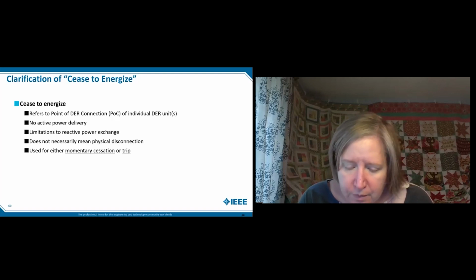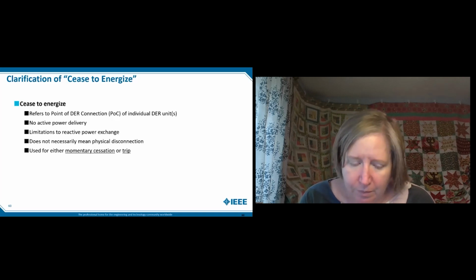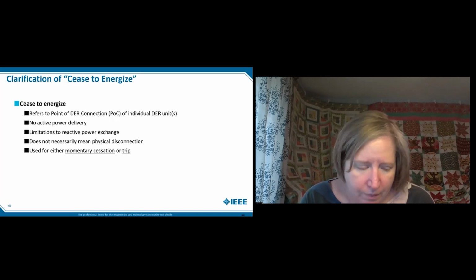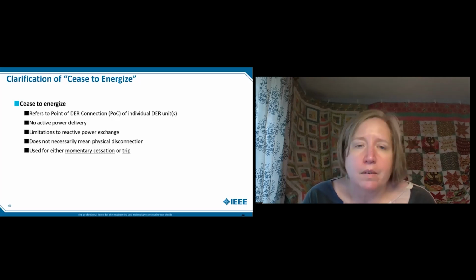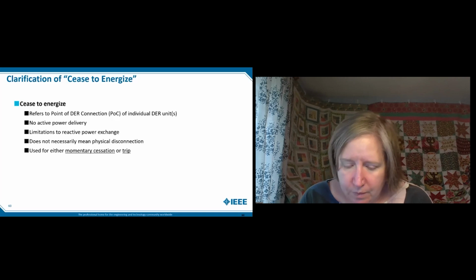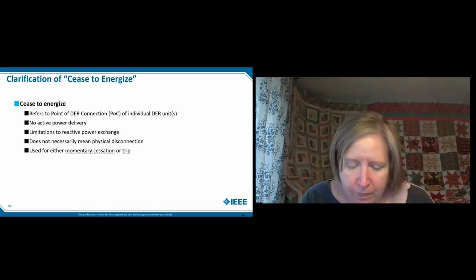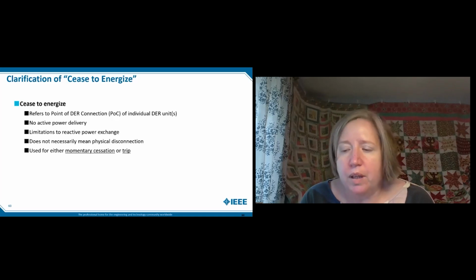And again, VARs don't move. So if you've got a voltage VAR problem, they tend to be localized and you're not going to fix it at the system level. That's what our utility was running into, feeder by feeder, telling people, look, we can't take any more PV. At the local level, they might have been at 20%, but the system was well under 3% penetration. But localized, you will run into problems before you have a collective system-wide operating challenge.